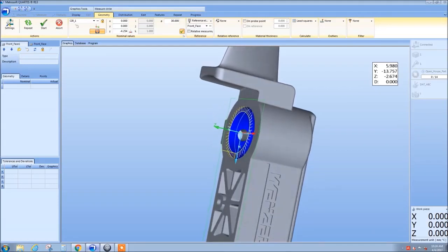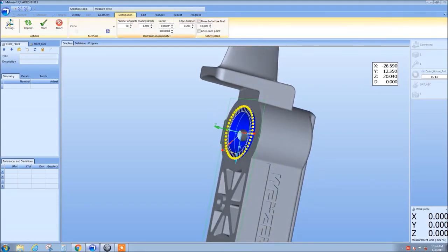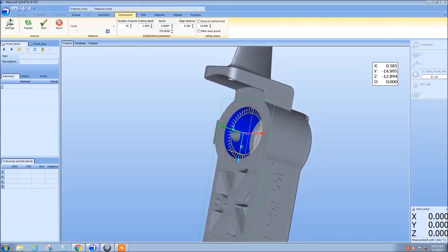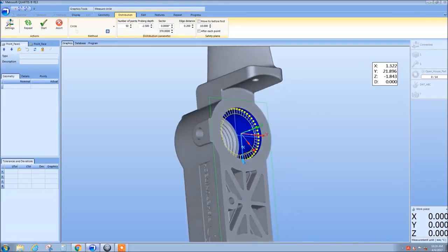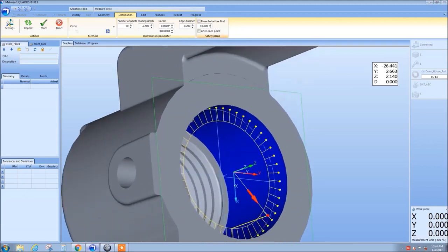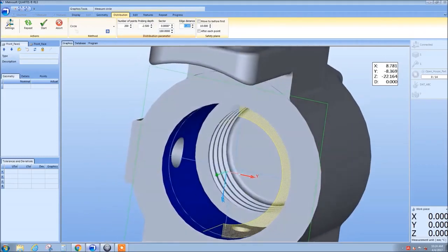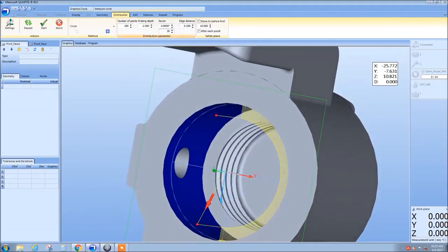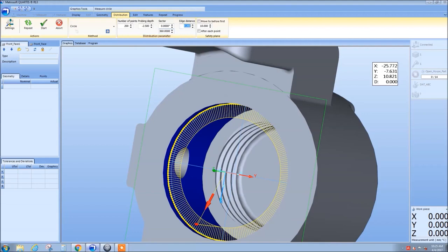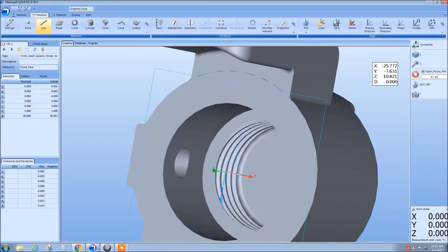And by just one click on that green button, the points are already collected from the scan data of the real part, in the memory of the computer. This goes quite quickly as it is a virtual process. Normally on a CMM, it would take quite a long time to sample hundreds or thousands of points. Here, this goes in a few seconds.